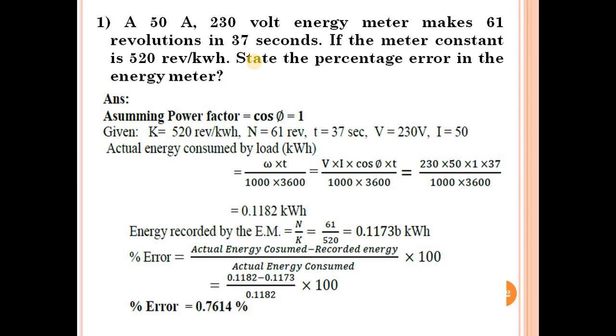Now we will see how to solve it. Assume power factor cos phi is equal to 1. Given: K meter constant value 520 per kilowatt hour, N = 61 revolutions, time = 37 seconds, voltage = 230, current = 50. Now we can calculate the actual energy consumed by the load in kilowatt hours. The formula is W into T divided by 1000 into 3600.